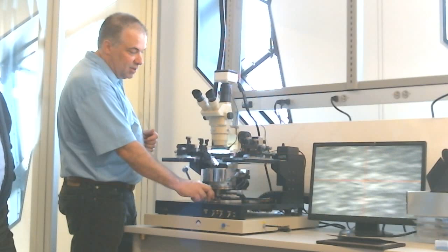On the back left of the bridge here, there's a knob that will allow you to move this probe platform up and down. This lever will move from the bottom all the way to the top, which is 3 millimeters. There's also a lock at the top. If you rotate it 90 degrees clockwise, it'll lock this lever in place so you can't accidentally lower it, or if you lean on this or accidentally hit the lever, it's not going to bring your probes down. Turn it back 90 degrees counterclockwise and move it down, and there's an intermittent stop before you get to the bottom that's 300 microns off your substrate.